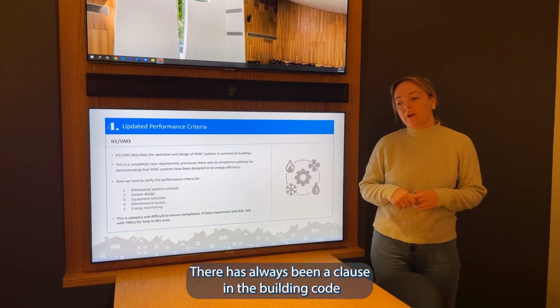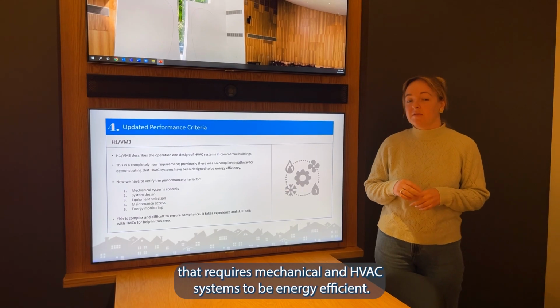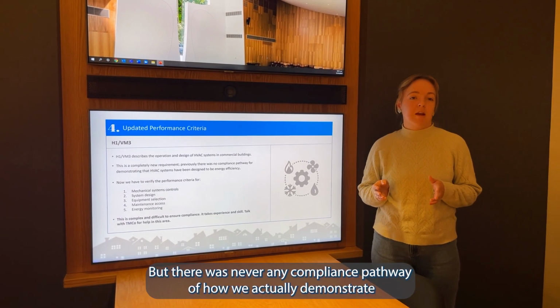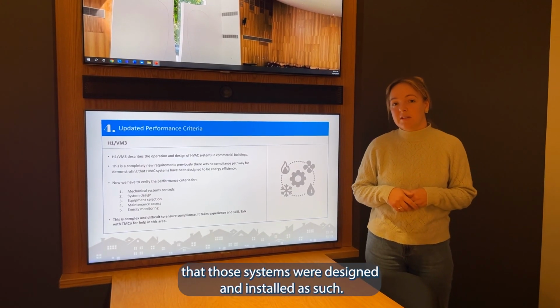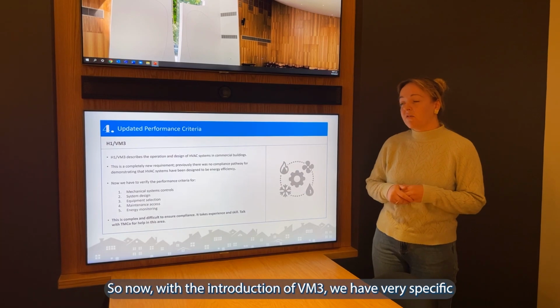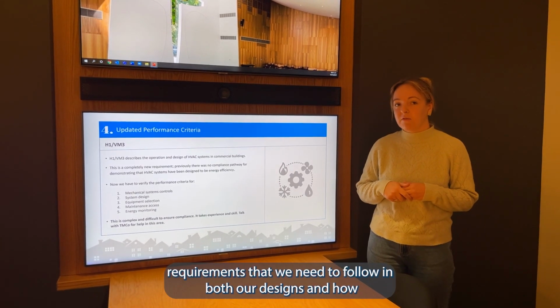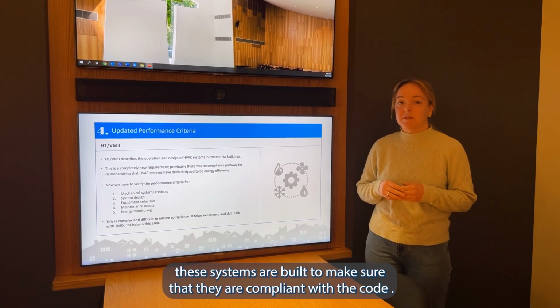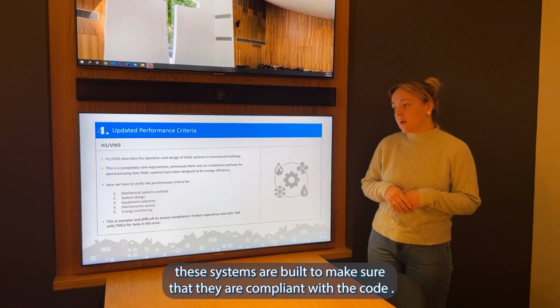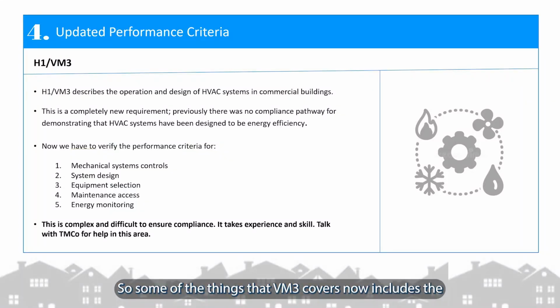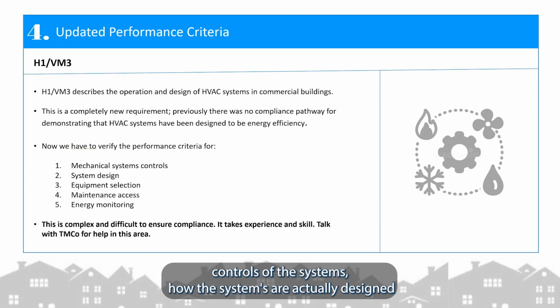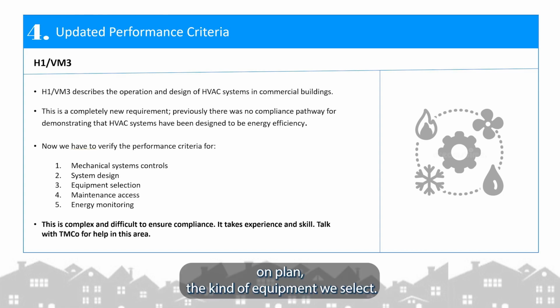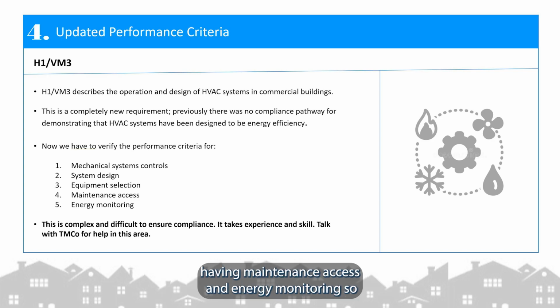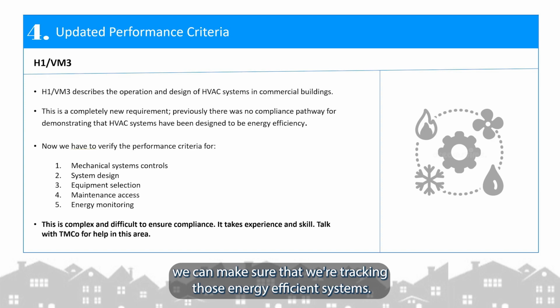There has always been a clause in the building code that requires mechanical and HVAC systems to be energy efficient, but there was never any compliance pathway of how we actually demonstrate those systems were designed and installed as such. So now with the introduction of VM3, we have very specific requirements that we need to follow in both our designs and how these systems are built to make sure that they're compliant with the code. So some of the things that VM3 covers now includes the controls of the systems, how the systems are actually designed on plan, the kind of equipment we select, and then going forward through the life of the building, making sure that we're having maintenance access and energy monitoring, so we can make sure that we're tracking those energy efficient systems.